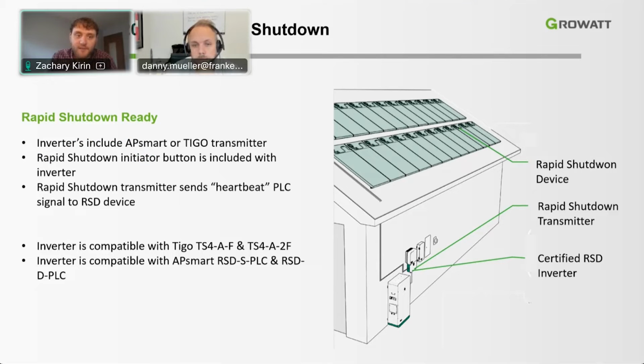The rapid shutdown transmitter sends that heartbeat signal for the PLC devices up on the roof. So each of the rapid shutdown devices will be sensing that heartbeat signal. And then either when the rapid shutdown initiator button is pressed or when the DC disconnect of the inverter is turned off, that signal will no longer be present on the roof, and each of those rapid shutdown devices will turn off. Okay, so they'll no longer be sending their full voltage down to the inverter.